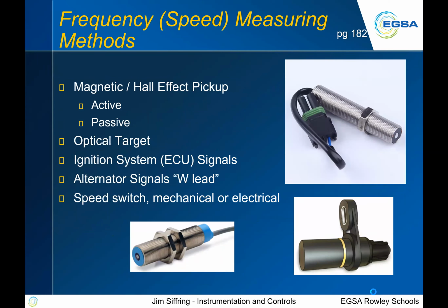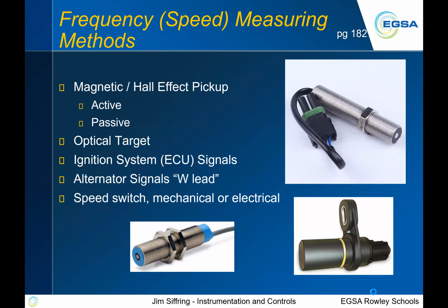Frequency measuring. So how do we measure, say, RPM on a gen set? So, magnetic Hall effect pickup. There's a couple of different ways. Active ones, which is basically a powered device, or passive, which is like what you see in the upper right graphic there. Generally speaking, it's a piece of steel with a little bit of a magnetic charge to it, or it is magnetic, I'm sorry, and then has a coil of wire around it, about a zillion wraps of really fine wire around it.